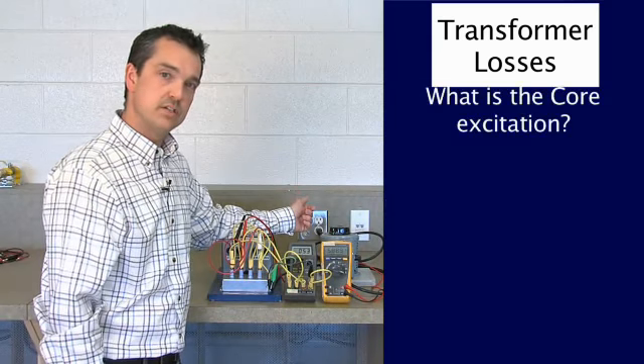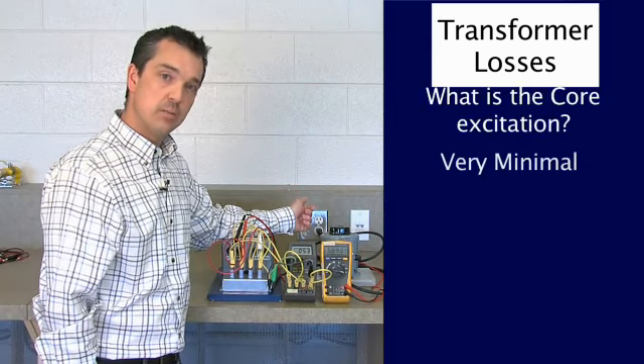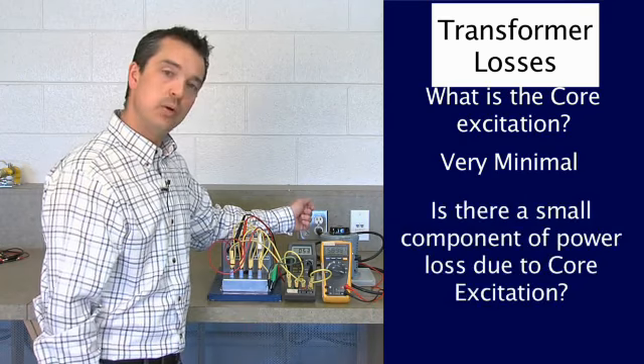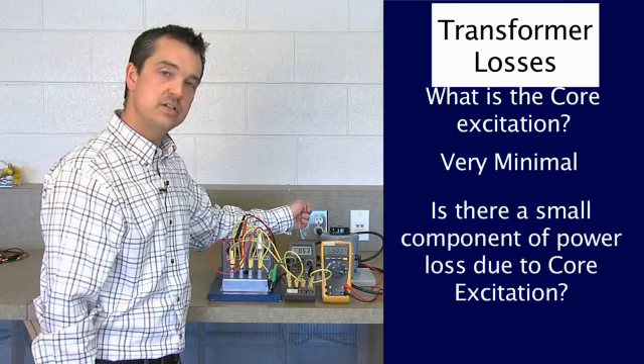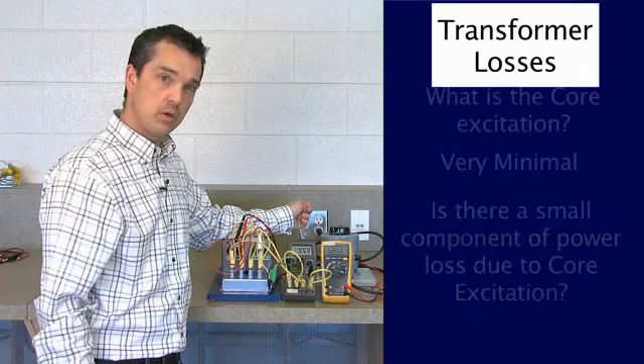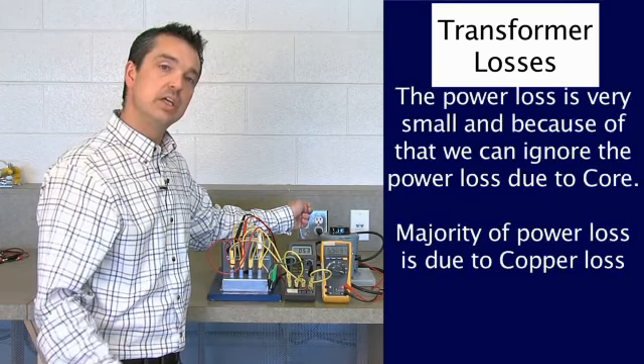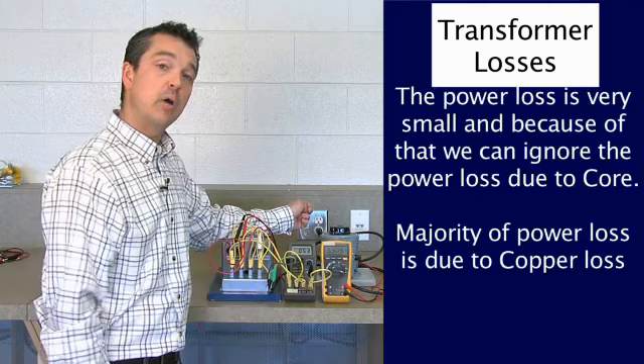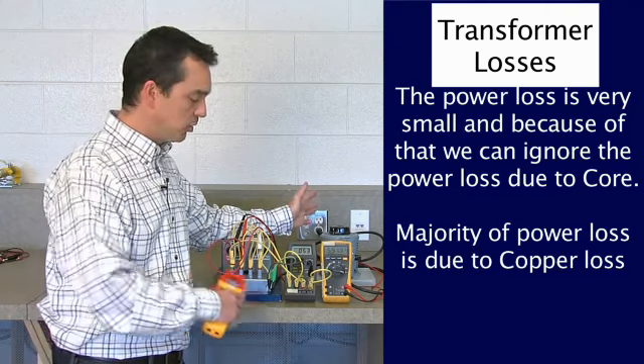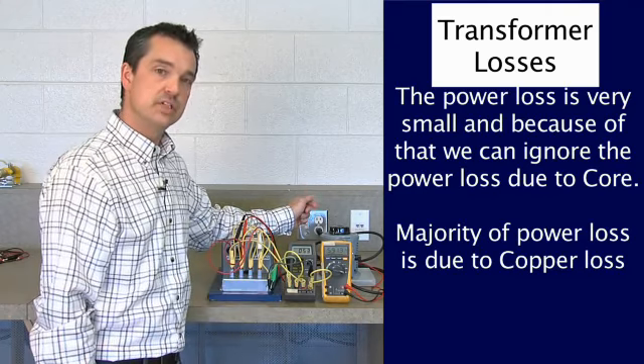What's my core excitation? It is very, very minimal. So is there a small component of power loss here due to core excitation? Sure there is, but it's very small. And because of that, we can ignore the amount of power loss due to core. The majority in this test is due to a copper loss condition.